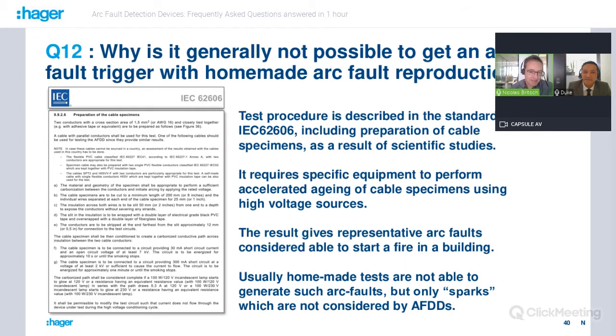Because in the standard, there is a test procedure which is described, and it also includes the preparation of cable specimens. And this is the result of scientific studies. So it requires specific equipment to perform accelerated aging of the cable specimens using high voltage sources. And the results give a representative arc fault considered to be able to start a fire in a building. And usually, homemade tests are not able to generate such arc faults, but only sparks.